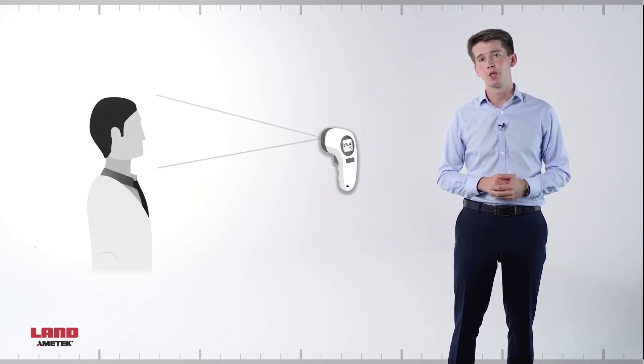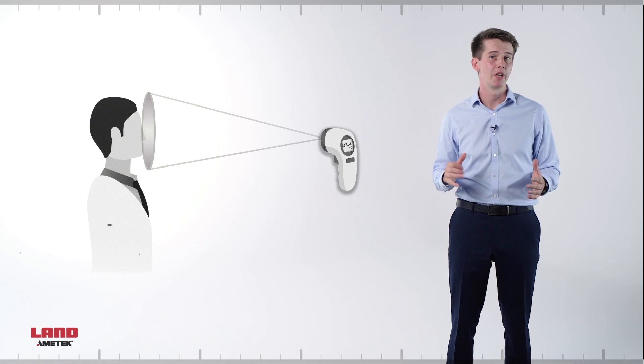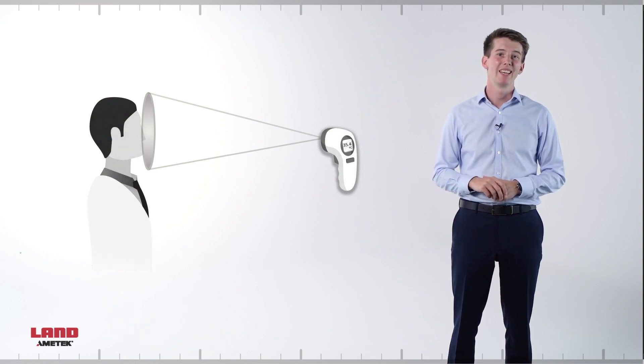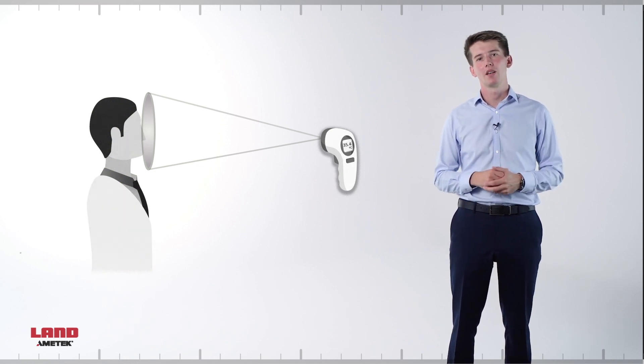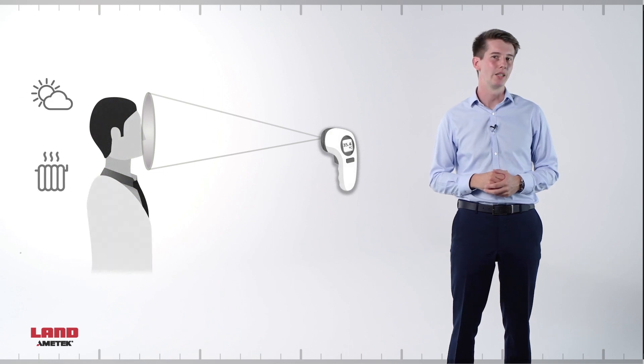Non-contact thermometers often have a large measuring spot. They provide an average measurement across the person's face even when used up close. Additionally, the measurement might include some background temperature. The accuracy of this measurement is further affected by the operator who may not hold the device in the same angle each and every time since they must adjust to measure different people. The issue is magnified between shifts and multiple operators.